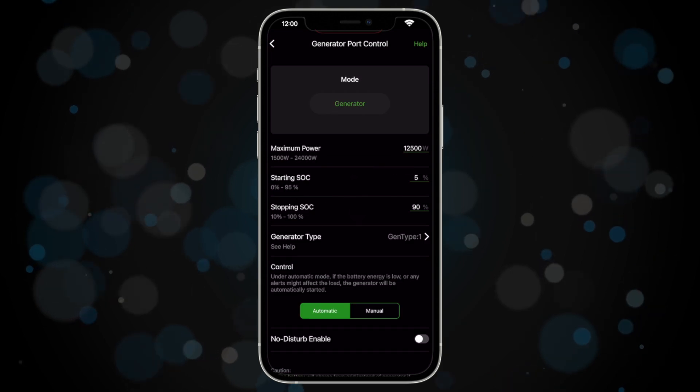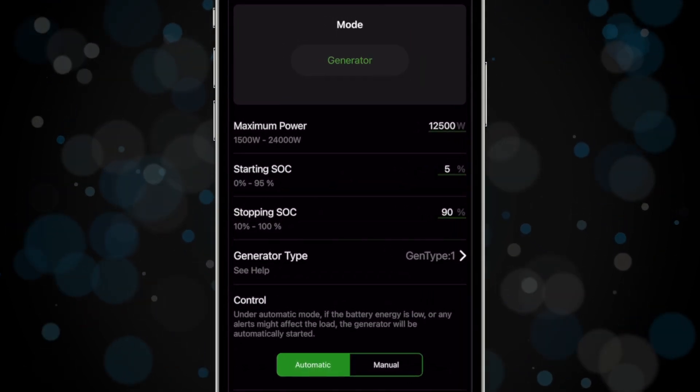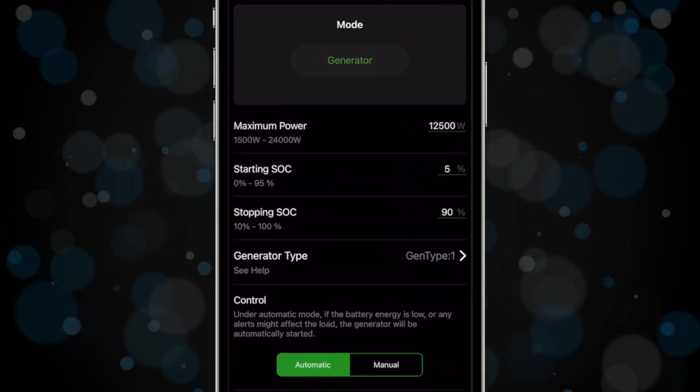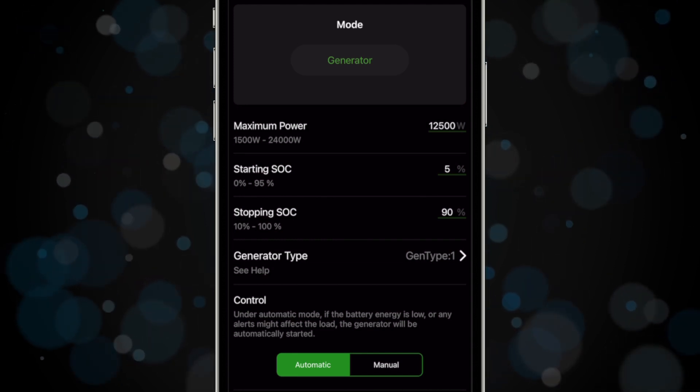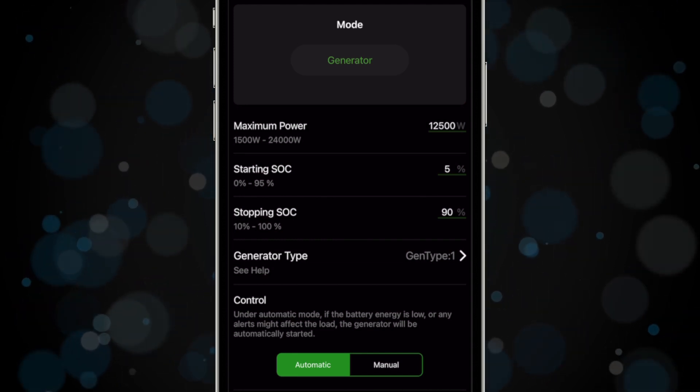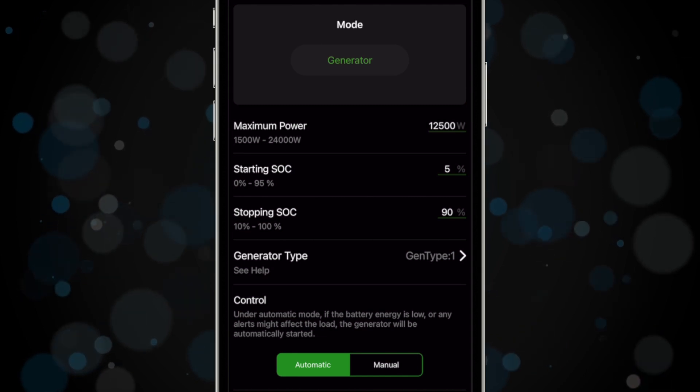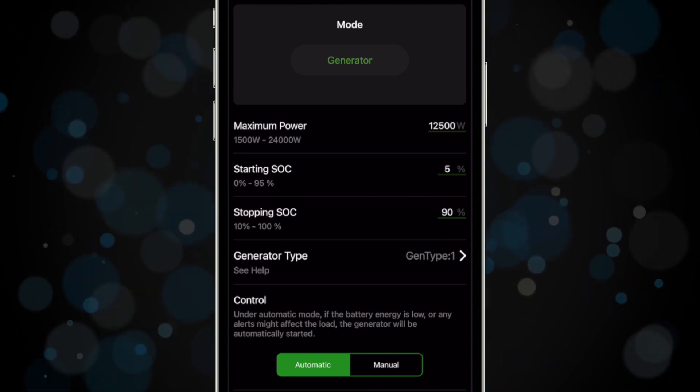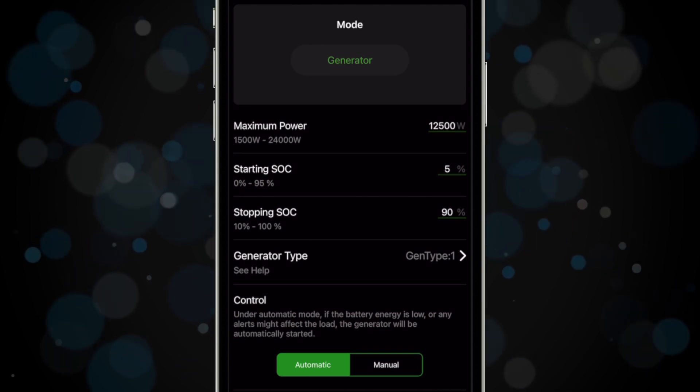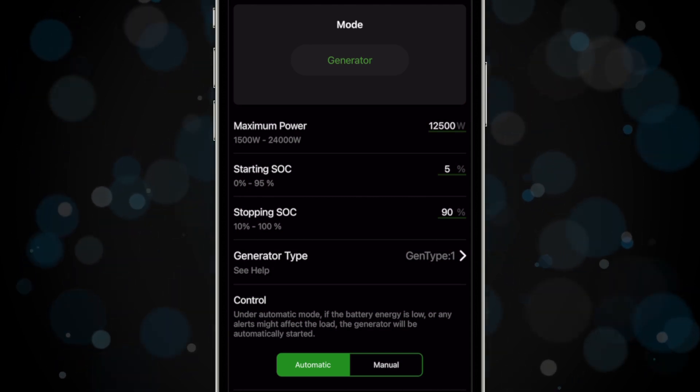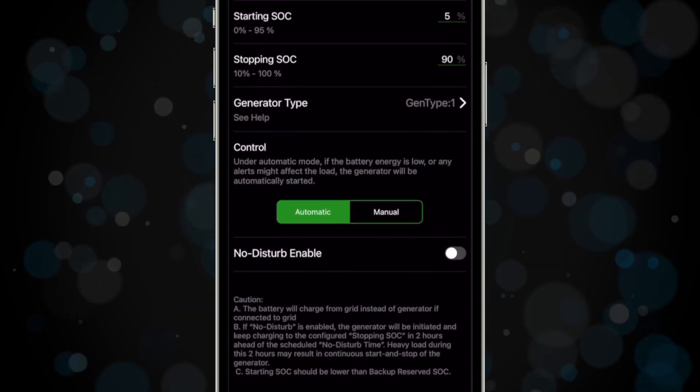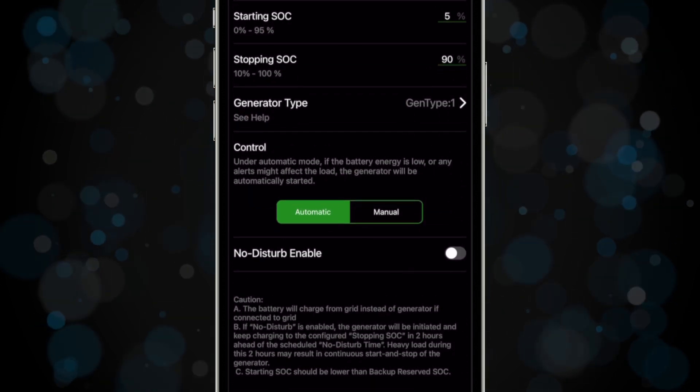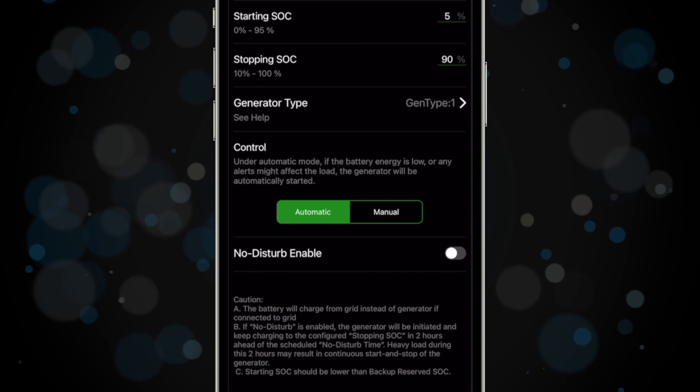Ensure the following settings: Set the mode to generator. Set your starting SOC or state of charge—this is the battery charge level at which the generator will turn on to recharge the battery. Set your stopping SOC—this is the battery charge level at which the generator will turn off and stop charging the battery. Set the generator type to gen type 1. Set control to automatic. This will trigger the NO1 port and COM1 port to close, sending the signal to start the generator.